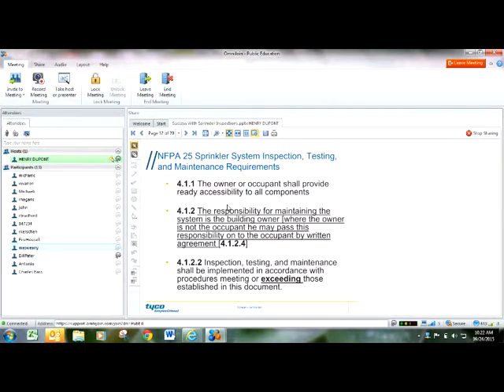Companies like us are always being sued because sprinkler systems don't work the way they were designed to work because of lack of maintenance. Whereas the sprinkler contractor can be writing up deficiencies and handing them to the building owner. The building owner is under no obligation to fix those things, no obligation to us. He's under obligation to fix them to be in compliance with code and local jurisdictions, but they don't necessarily have to. I like to think that if you're in a state-regulated building, you stand a much better chance of getting out of that building in a fire because it's being required to be maintained. If you're in a grocery store, there's no guarantee that anybody is forcing that sprinkler system owner to maintain their sprinkler system.